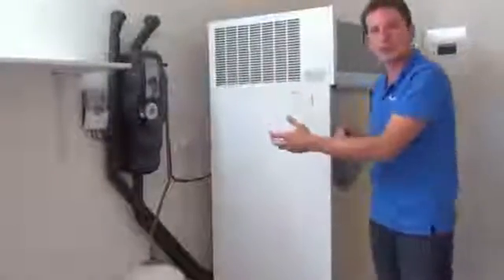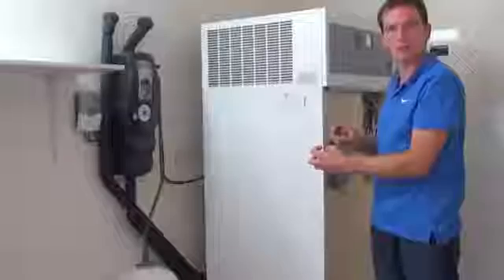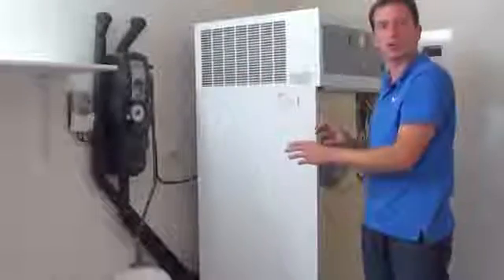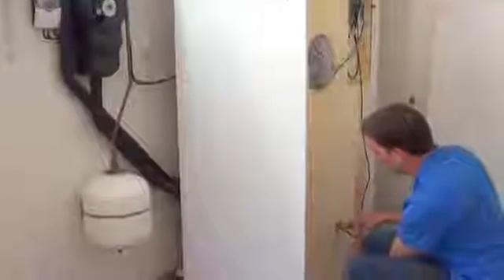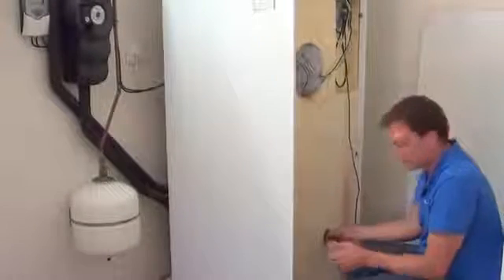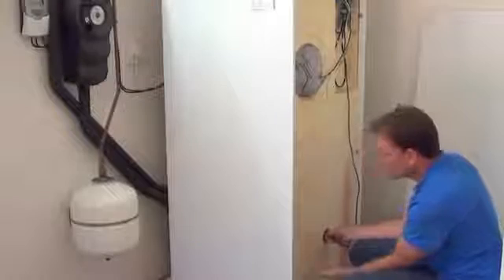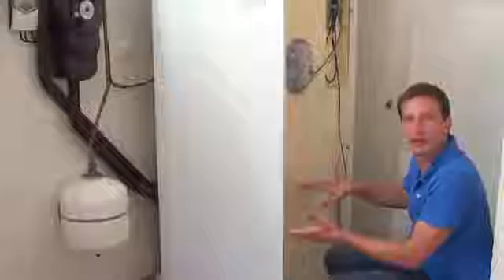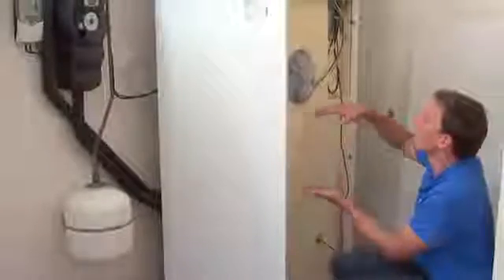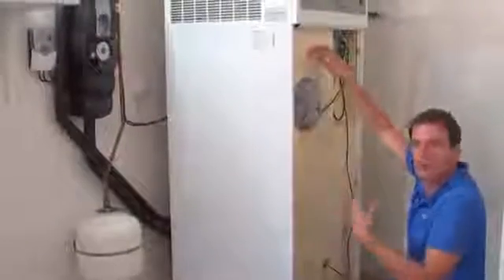Now the secret of the system, or where the secret comes in, is that we are marrying these two systems without them knowing what the one is doing with the other. If cold water comes into the bottom of this tank, the cold water from the municipality is going to obviously rise up to the top. It's going to go past the sensor. If the sun is shining, it will contribute the heat into the bottom of the tank, and the heat will automatically, through specific gravity, rise up to the top of the tank through the natural layering effect of water.